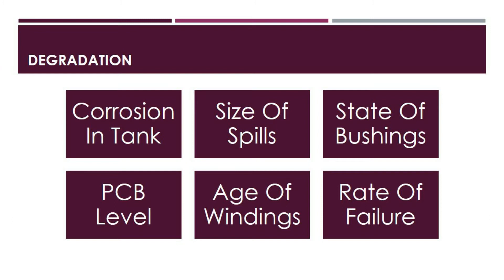When calculating the health index for distribution transformers, the following elements should be taken into account: the corrosion in the tank and the state of the paint of the tank, the size of the oil spills, the state of the bushings, the PCB level of the transformer, operational age and temperature profile of the windings, and the rate of failure.